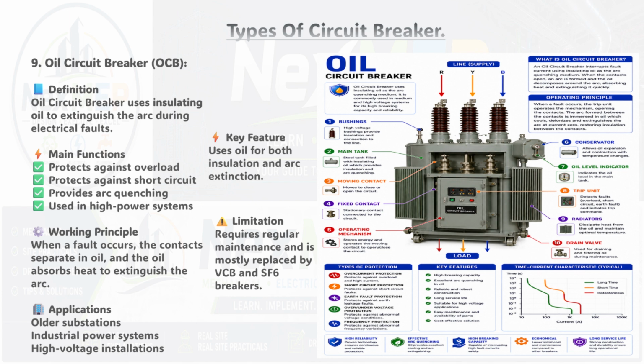Now, what's the limitation? OCBs require regular maintenance. The oil needs to be checked, filtered, and replaced periodically. They're bulky, heavier, and have a fire risk if oil leaks. That's why today, OCBs are mostly replaced by VCBs and SF6 breakers in modern systems. But understanding OCBs is important for maintenance engineers working with legacy systems.